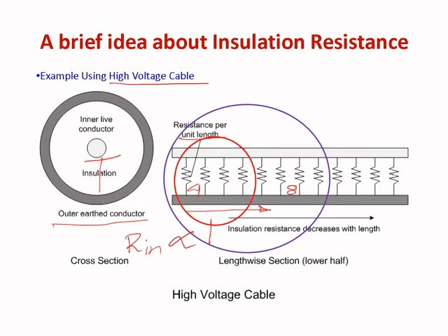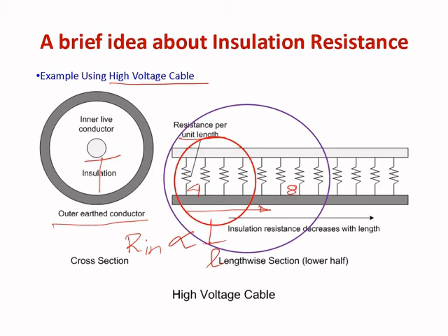If the number of resistances connected in parallel increases, it means the net effective resistance decreases. So from that we can conclude that the insulation resistance of the high voltage cable or any insulating material is inversely proportional to the length of the cable or length of the insulating material. That concept is essential when we want to solve numerical problems based on this.